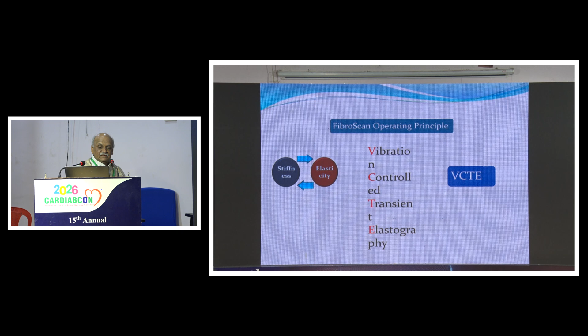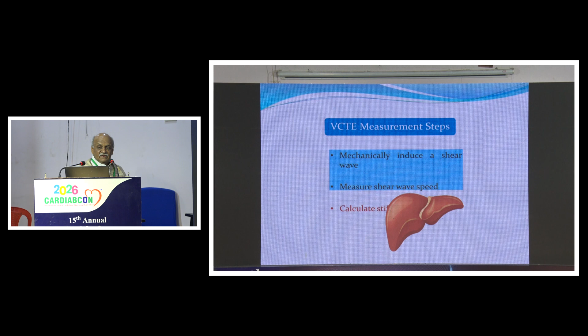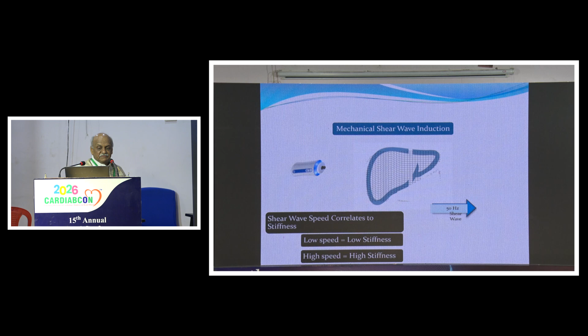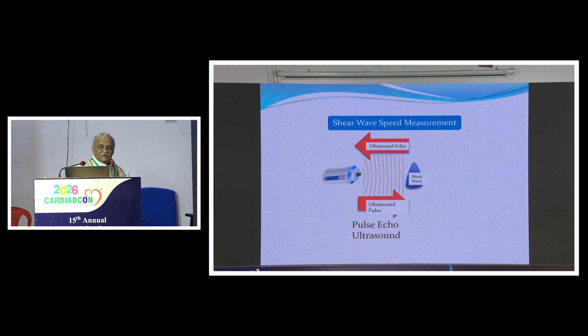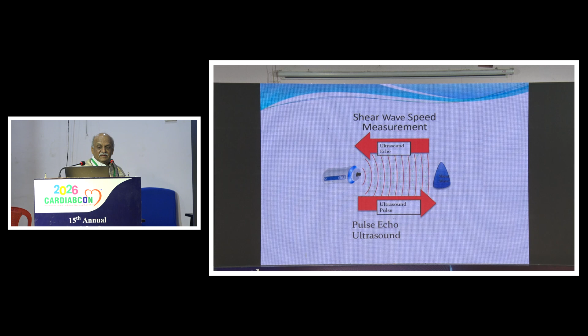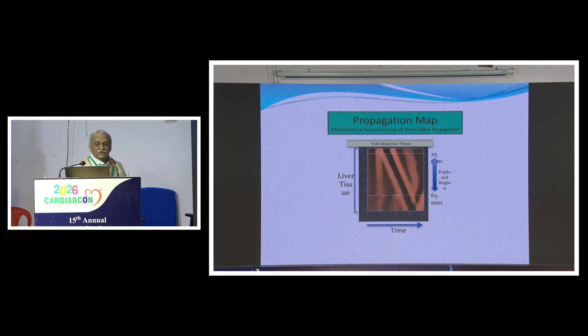So FibroScan operating principle, I told you already, is vibration controlled transient elastography. It measures stiffness. It is also known as VCTE. So mechanically induce the shear wave, measure shear wave speed, calculate stiffness. Shear wave speed correlates to stiffness: low speed means low stiffness, high speed means high stiffness. This is how it is measured, and this is ultrasound echo and ultrasound pulse is recorded. This is propagation map, mathematical reconstruction of shear wave propagation.